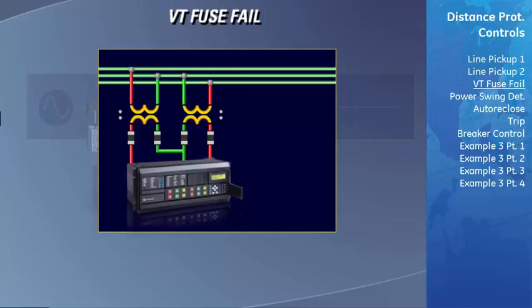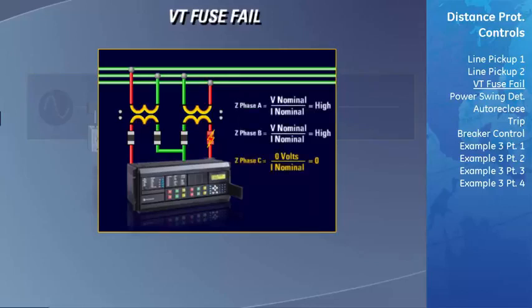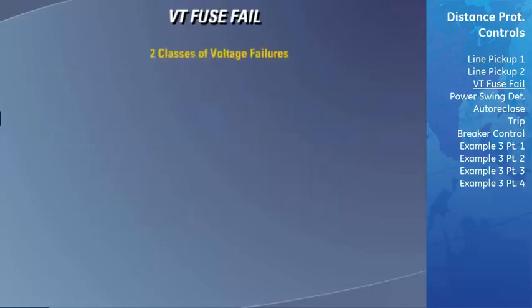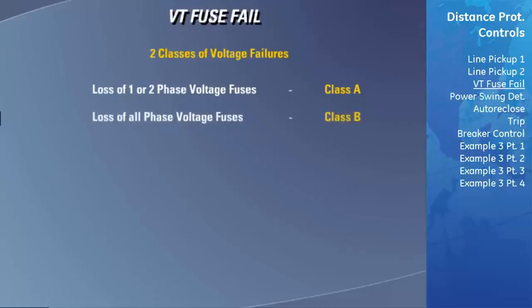If one or more of these fuses were to blow, the D60 would not read any voltages on that phase. Now if the D60 were to perform its impedance calculations, the equation using the phase with the blown fuse would result in an impedance of 0. This 0 impedance would fit into the D60's Zone 1 area of protection, which would then proceed to cause the breaker to trip immediately. There are 2 classes of fuse failures that can occur. The first type is when there is a loss of 1 or 2 phases of voltage due to blown fuses. This is known as a Class A fuse fail. The second class is when there is a loss of all 3 phases due to all 3 fuses blowing. This is known as a Class B fuse fail.